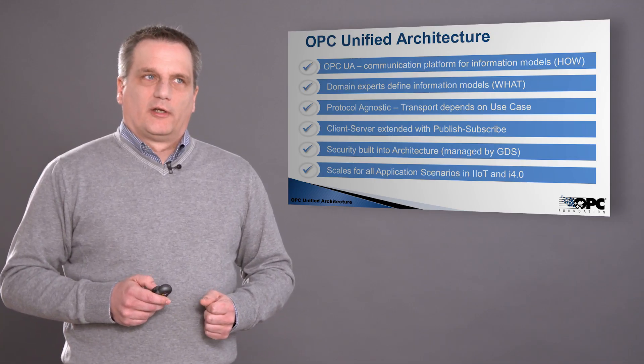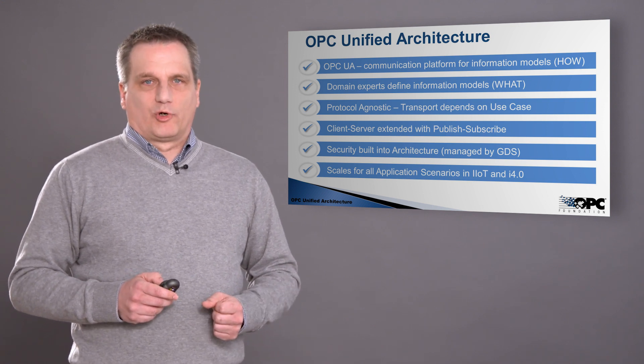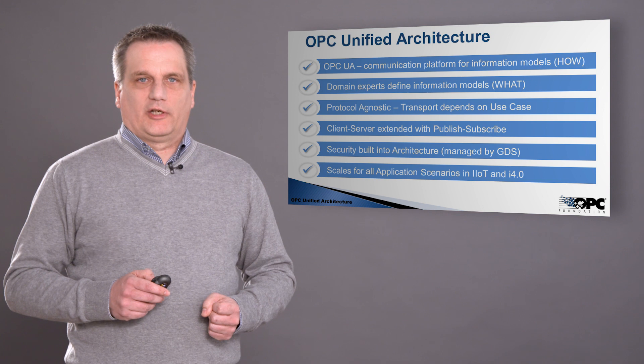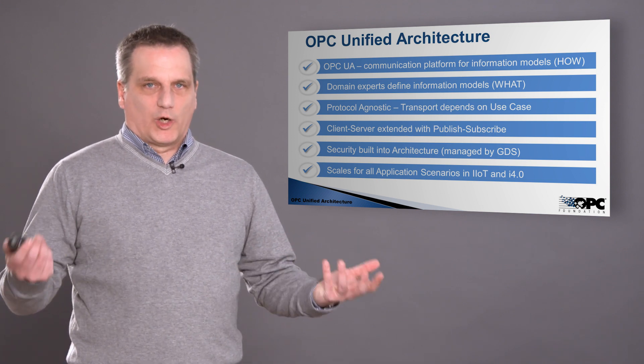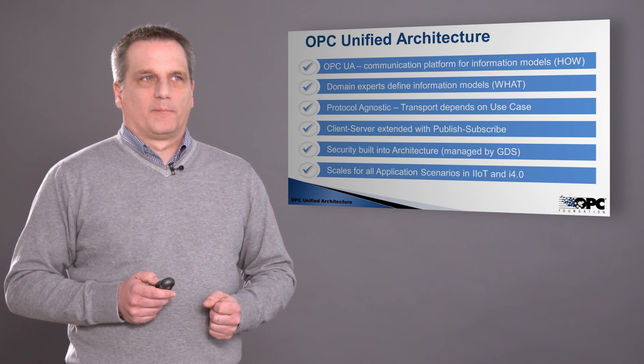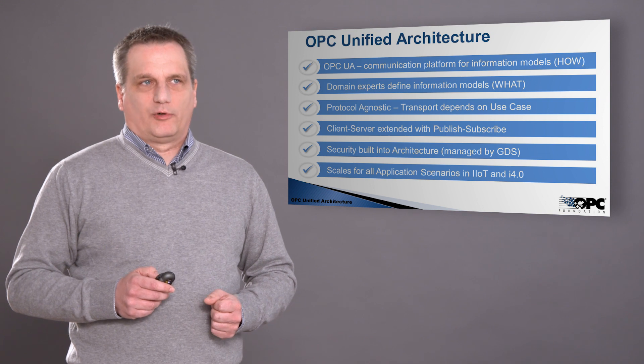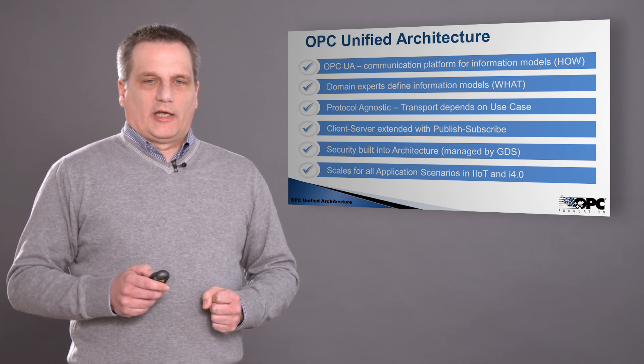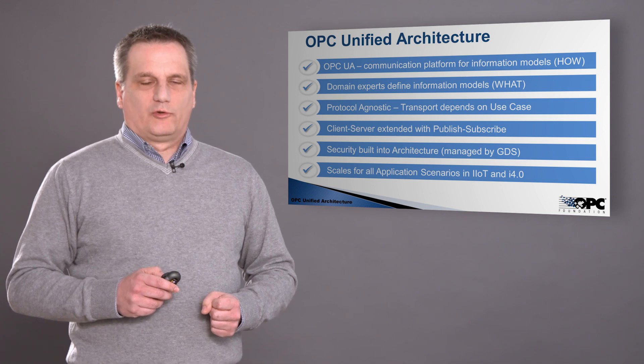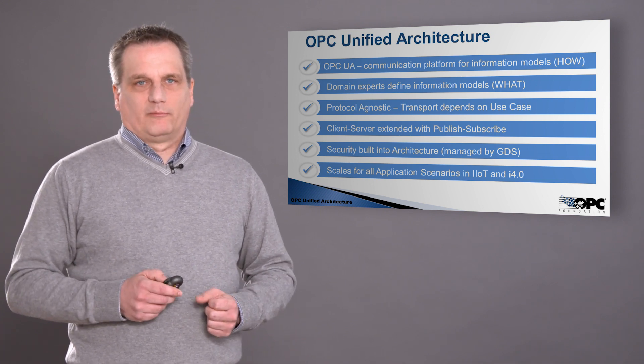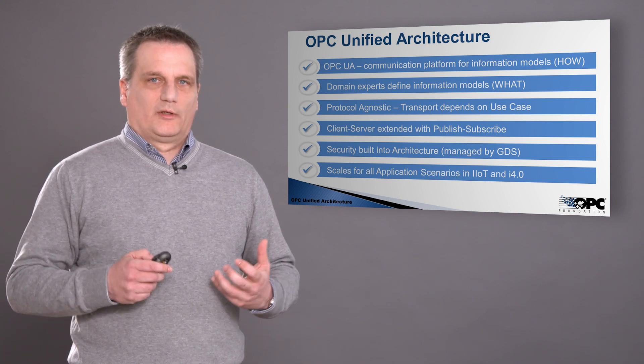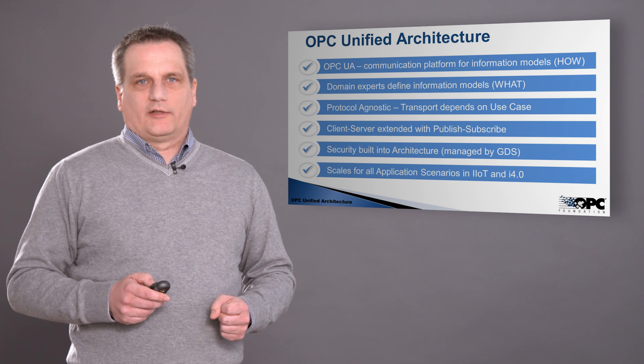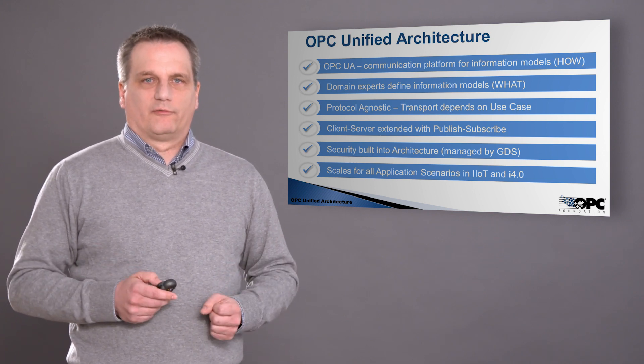To summarize: OPC Unified Architecture is a communication platform for information models which define how information is described, with domain expert and companion specifications sitting on top of that to describe what kind of information is to be exposed. It is protocol agnostic, so we have different transports depending on the use case. You can either use the client-server model, which has now been extended with the publish-subscribe communication model to cover all different use cases in all kinds of communication architectures. In addition, security is built into the architecture, and there is an additional tool called the GDS to manage this security from a central point in the network.